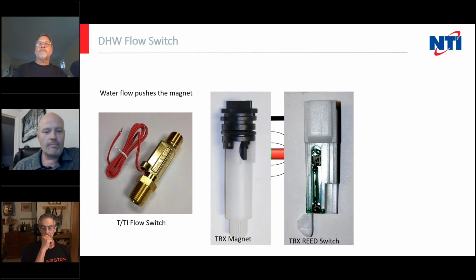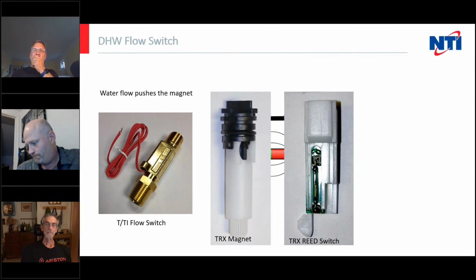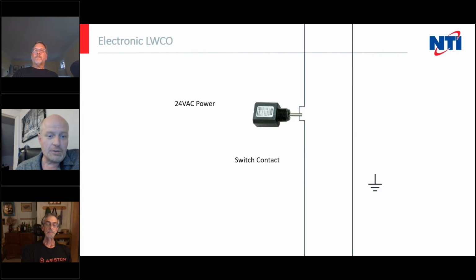And Dave, the other thing is, guys, you want to service that switch every year when you do a preventive maintenance. If you could pop it open, check it, clean it off. I've pulled them and seen crap in the bottom of them. And that's just preventive maintenance to prevent that thing from locking out. Yeah, and you won't get any error codes if this fails. All that'll happen is you'll turn on the tap and just nothing. You don't get hot water.